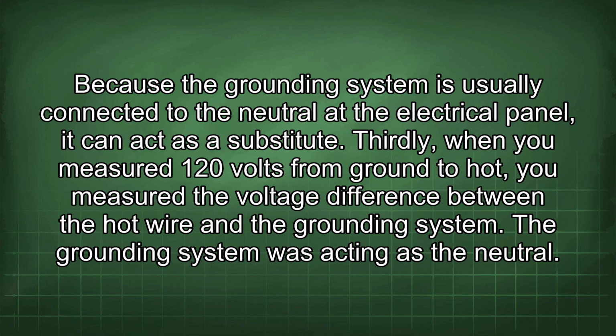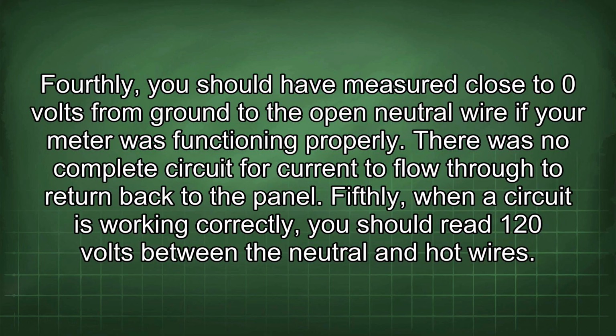Thirdly, when you measured 120 volts from ground to hot, you measured the voltage difference between the hot wire and the grounding system. The grounding system was acting as the neutral. Fourthly, you should have measured close to 0 volts from ground to the open neutral wire if your meter was functioning properly. There was no complete circuit for current to flow through to return back to the panel.